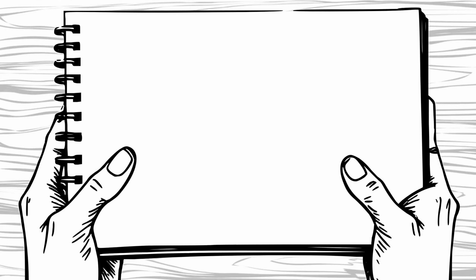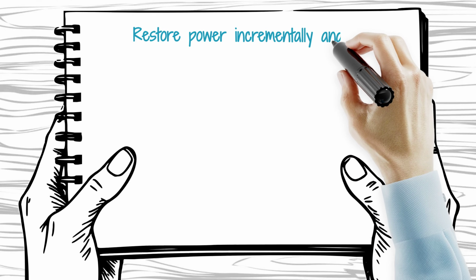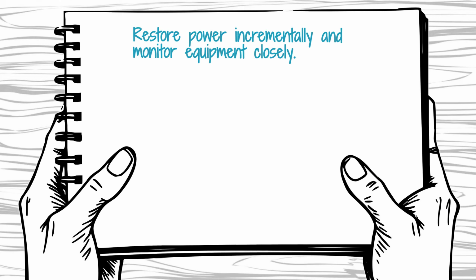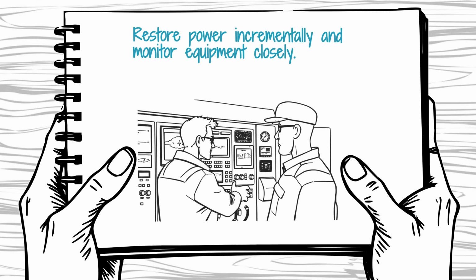The final step is recommissioning. Power must be restored incrementally, beginning with low-voltage tests. Closely monitor the equipment for any signs of arcing, heat, or abnormal operation. Only when all tests are satisfactory and the engineer is certain of the equipment's integrity can the system be returned to normal service.